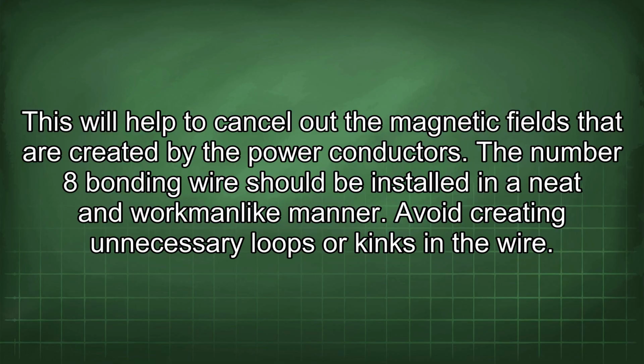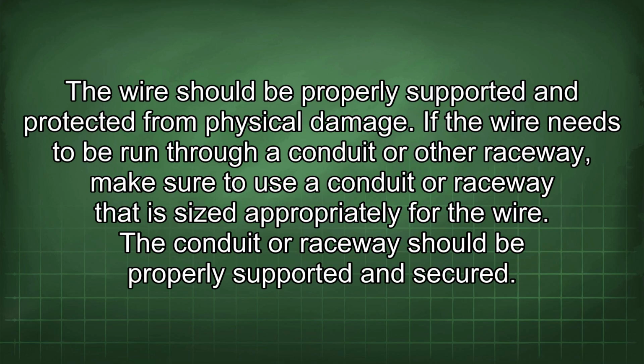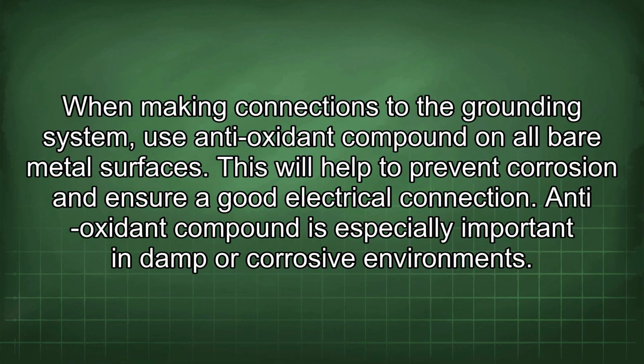The number 8 bonding wire should be installed in a neat and workmanlike manner. Avoid creating unnecessary loops or kinks in the wire. The wire should be properly supported and protected from physical damage. If the wire needs to be run through a conduit or other raceway, make sure to use a conduit or raceway that is sized appropriately for the wire. The conduit or raceway should be properly supported and secured. When making connections to the grounding system, use antioxidant compound on all bare metal surfaces.